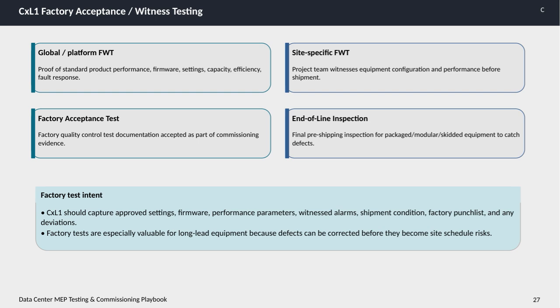Next, the site-specific factory witness testing involves a project team directly witnessing the equipment's configuration and performance before it even leaves the factory. This hands-on review helps catch any issues early. The factory acceptance test is backed by factory quality control test documentation. This documentation is a key piece of evidence during commissioning, confirming that the equipment met all required standards. We also have the end-of-line inspection, which is a final check before shipment. It focuses on packaged, modular, or skidded equipment to catch any defects that might have been missed earlier.